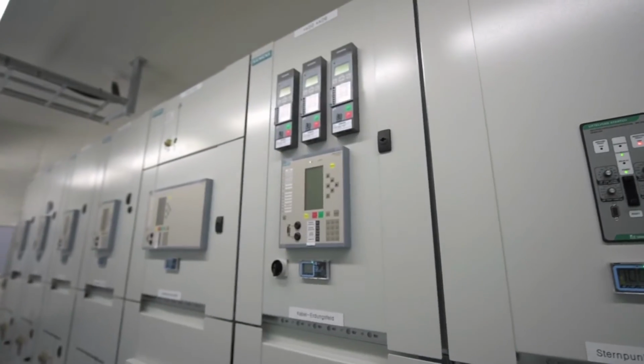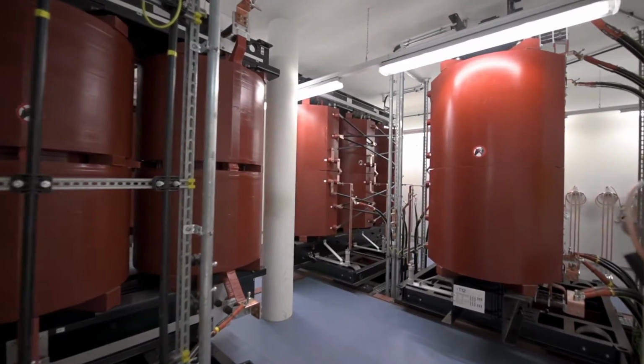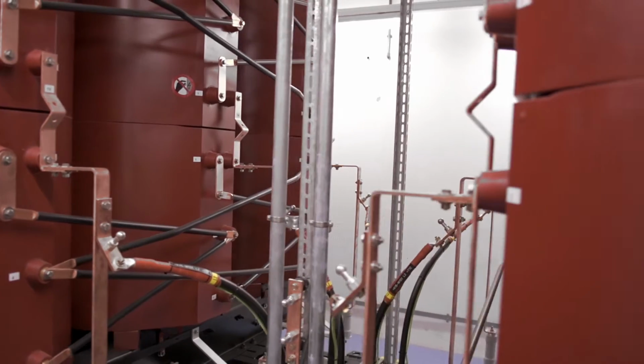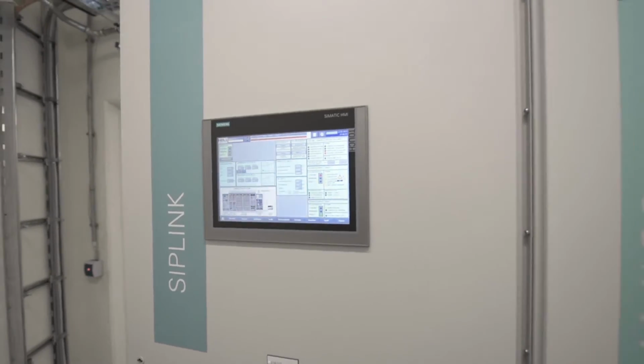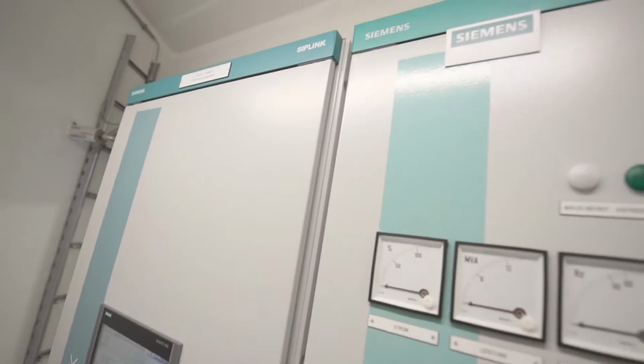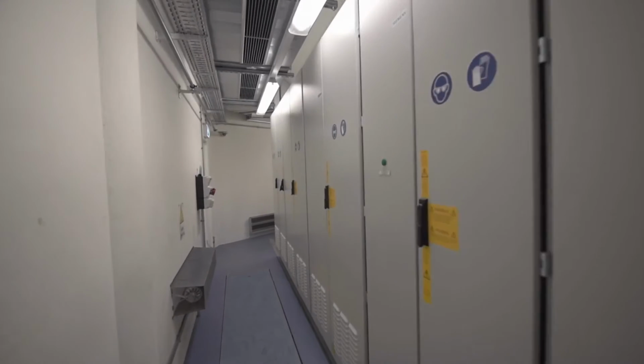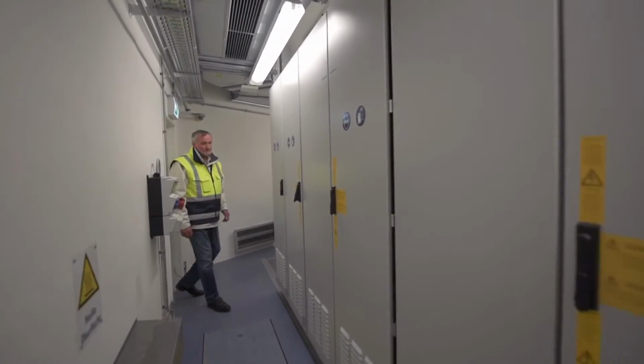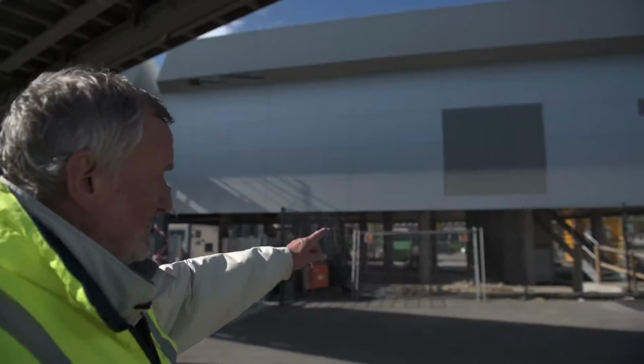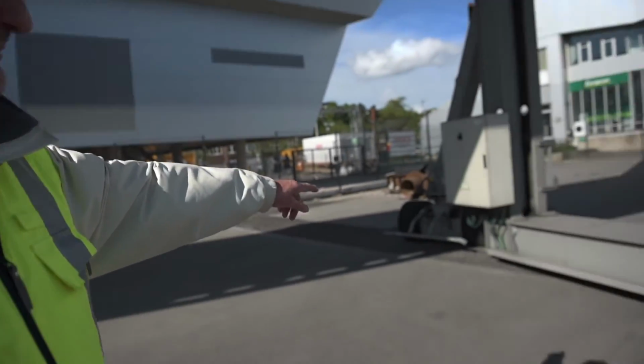Power is supplied to the 50 Hz medium voltage switchgear, from where it passes on to the 50 Hz transformers that transform the power to appropriate values for SIPLINK, which is the heart of the frequency conversion process. The SIPLINK output is converted into the appropriate frequency and voltage values and then passes via the output transformers and corresponding cables directly to the quay wall and onto the ship.